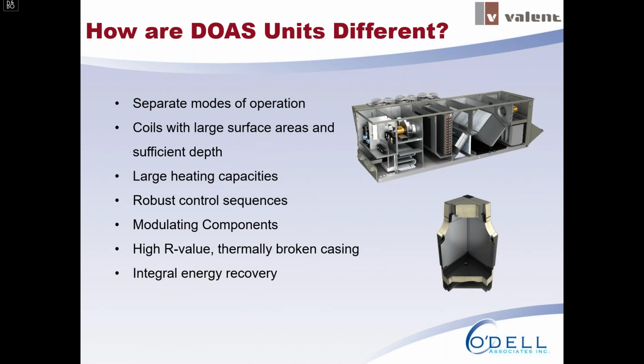So in addition to having separate modes of operation, dehumidification, cooling, and heating, which DOAS units can handle, there are some other key differences between DOAS units and standard packaged rooftop units. If you look at the coils, typically they're going to be sized with much larger surface areas and sufficient depth for handling dehumidification, because again, we're dealing with 100% outside air. We need that extra coil surface area and depth.